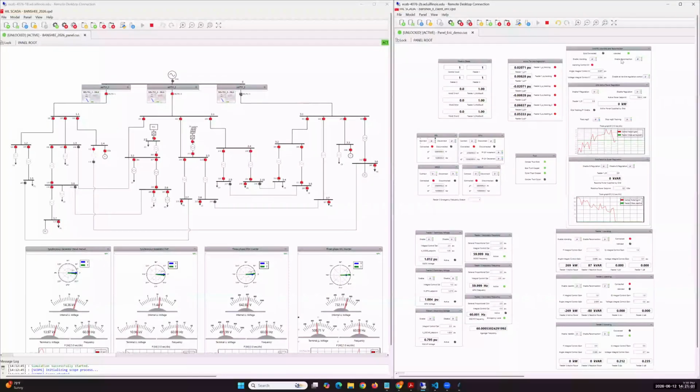We can see that up here, that feeder is islanded, and we can see that loss of trust persists. So that way we no longer trust feeder 3, and it is islanded on its own. So now we're running in 2 separate microgrids, one of which here is running distributed frequency control among these 2 feeders, and then this feeder over here is running just local frequency control.